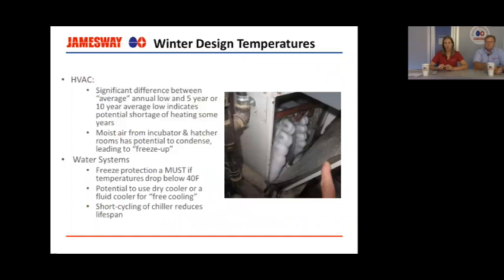Then your winter design temperatures. The first thing you need to make sure someone is looking at is what is the difference between the average annual low temperature and the 5-year or 10-year low. Because if every 5 years you're going to have a day or 2 days or 3 days or a week where you have a shortage of heating, that could cause a problem for you. So you may want to bump up your heating size, especially if you're kind of on the edge between two sizes, to make sure that you cover that.